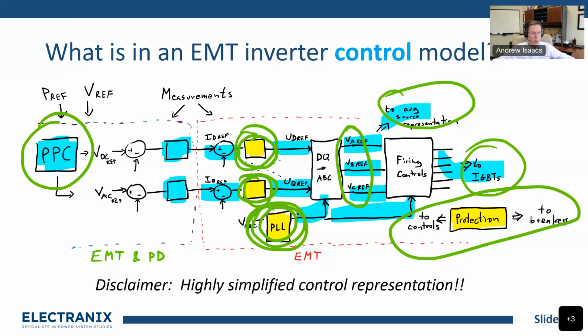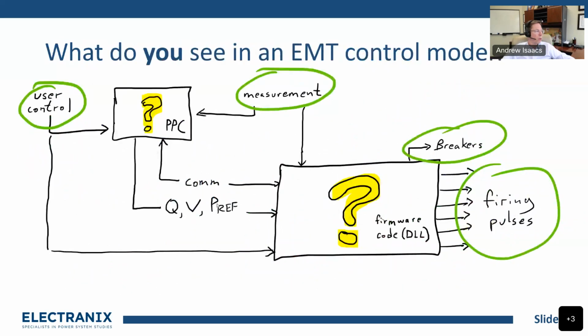Then we started to see system events happening, especially plants oscillating against other plants, identified by operating groups as relatively slow oscillations having to do with power plant controllers. These were significant events. Part of the issue was that the communication between the power plant controller and the inverters wasn't modeled right — there were delays in there.